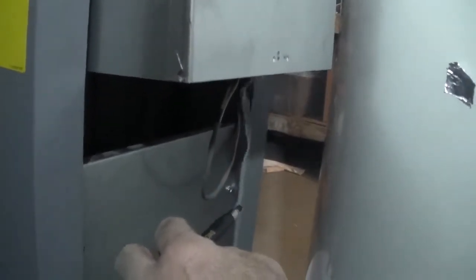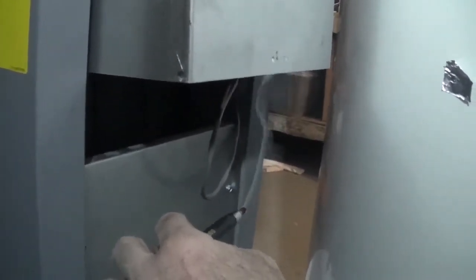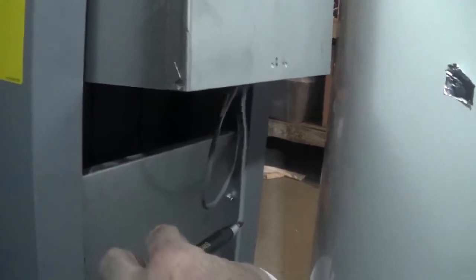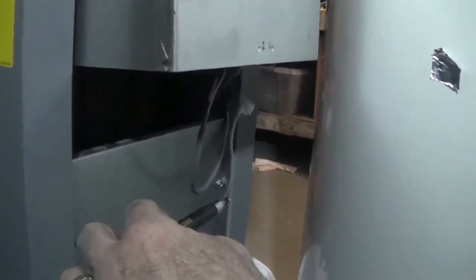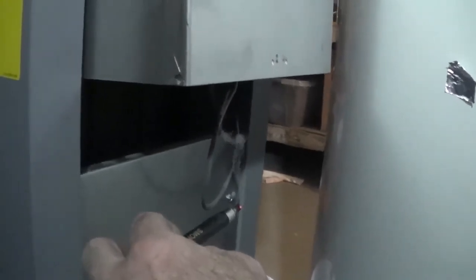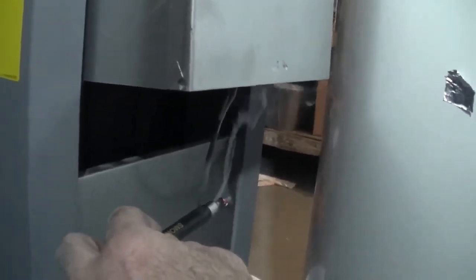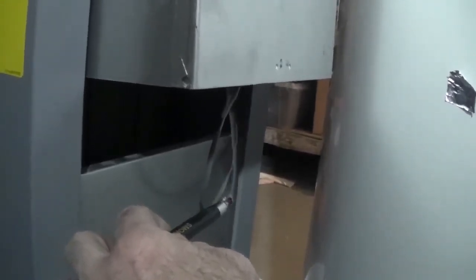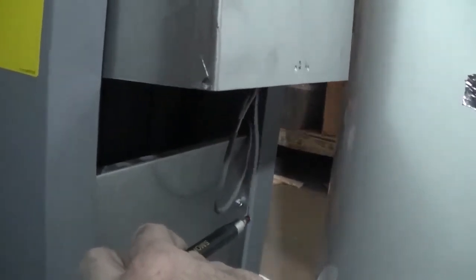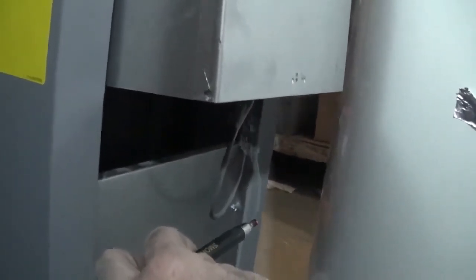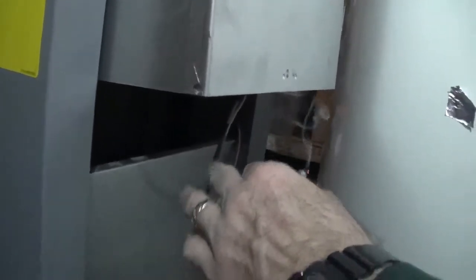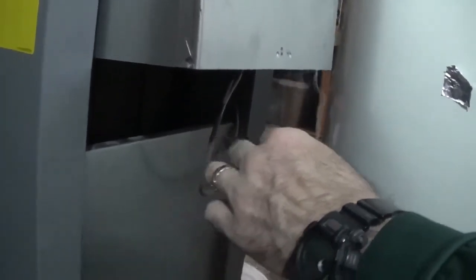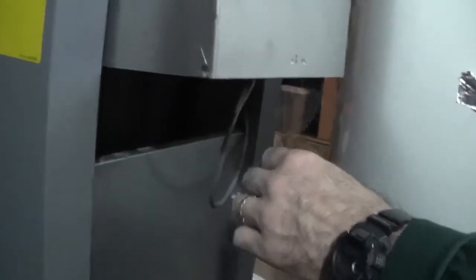I'm kind of right down on the line to see which direction it goes, in or out. It's kind of wavering between. Remember, we've got to give it 60 seconds because it may be heating up the flue enough to create a good draw for itself, and it's not done with that yet. But it's really close. It's been about 20 seconds or so. Not stellar. I can feel hot down here, so I know it's not perfect.